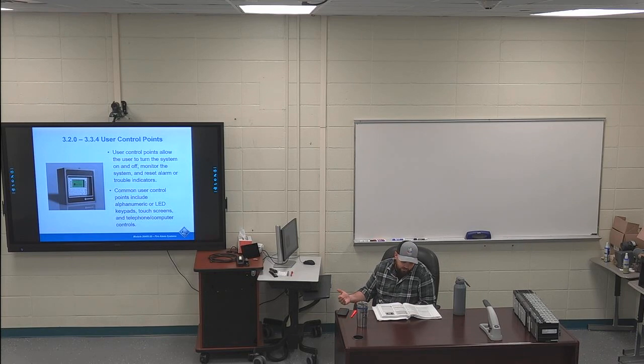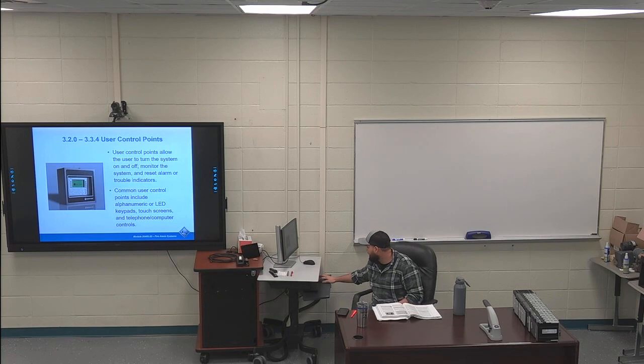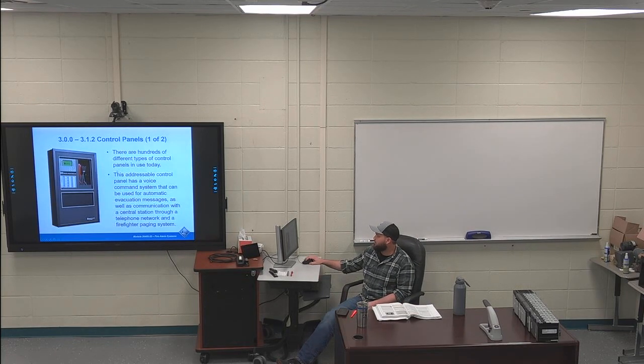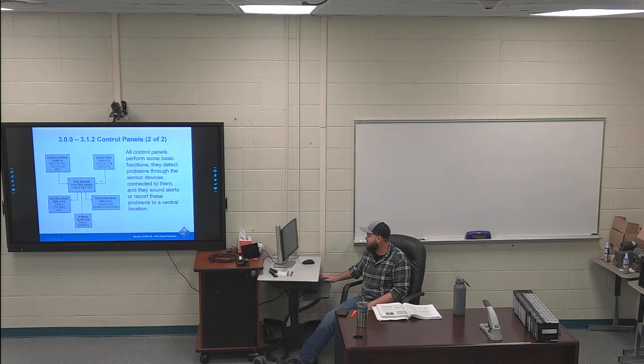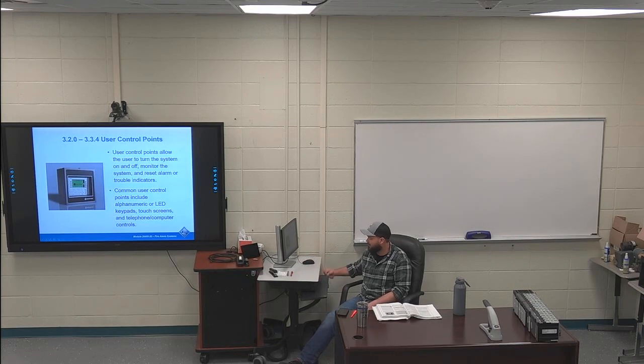The second note on page 25, right above 3.2.1, is highlighted. Underwriters Laboratories requires that any system controls that affect system operation be protected behind a locked door or locked out by a key. So they can't have 5-year-olds walking around being able to open up panels and mess around with fire alarm stuff. It has to be behind a locked door or locked out by a key. A lot of these panels, at least the panel that we have at Camp Hope, have a key. This door is keyed so that somebody can't just get inside of it.